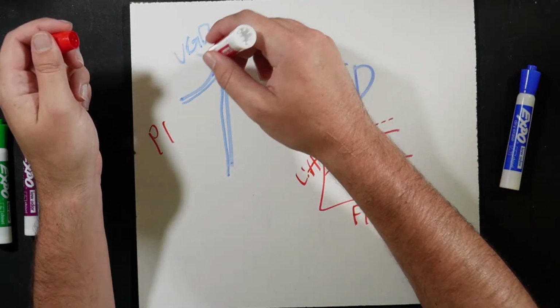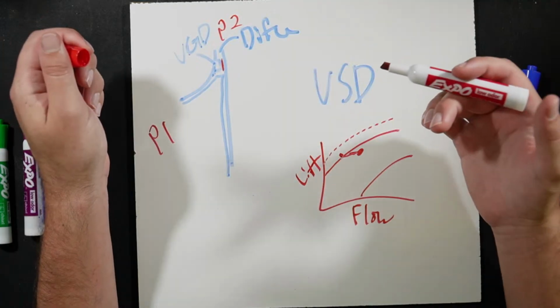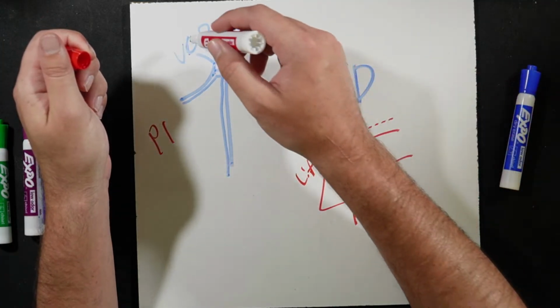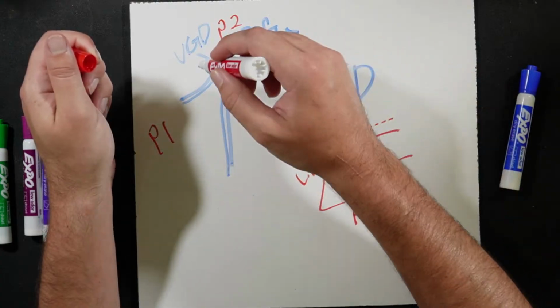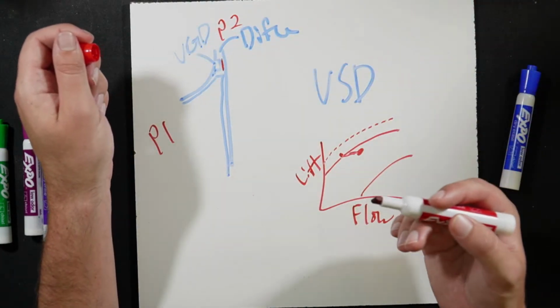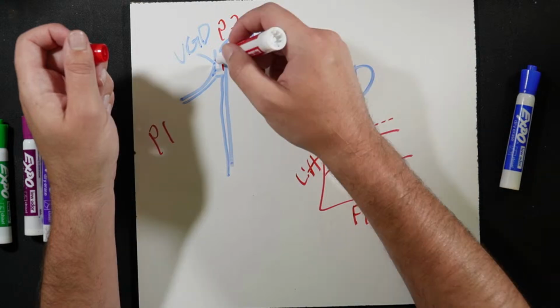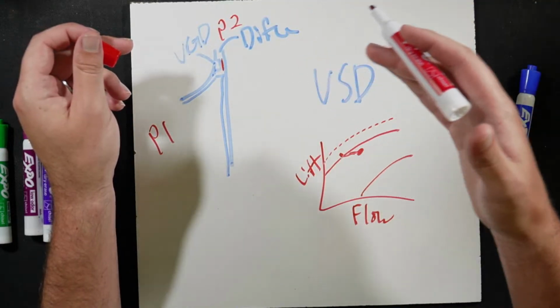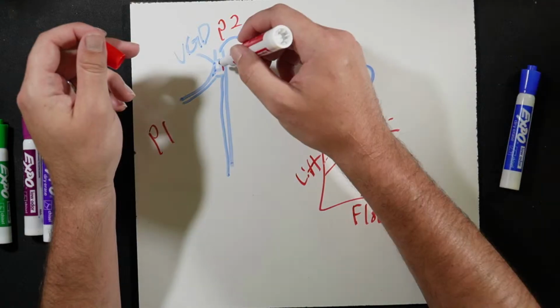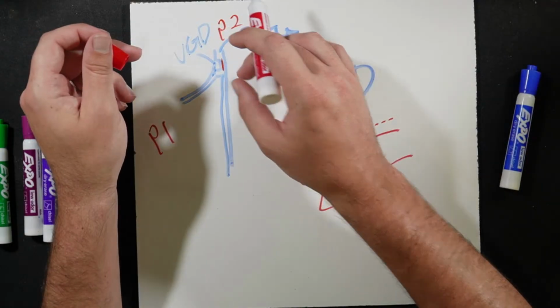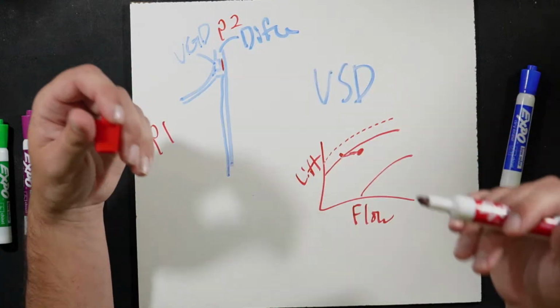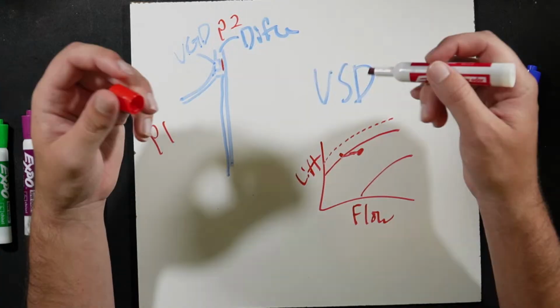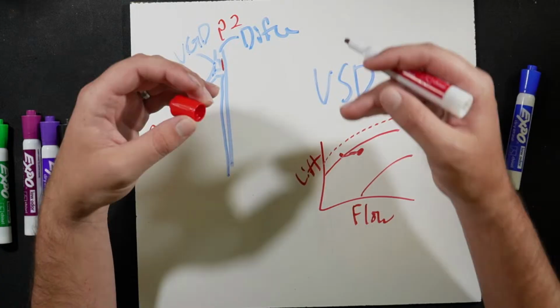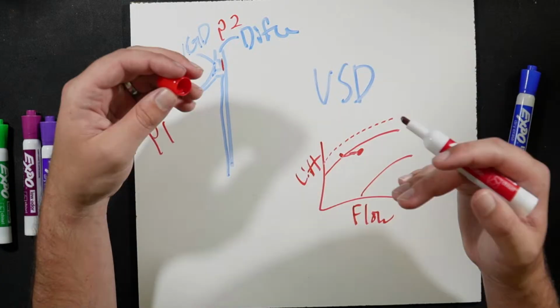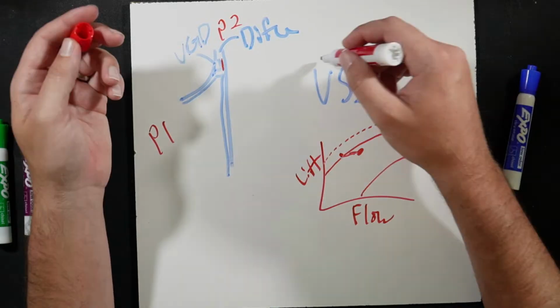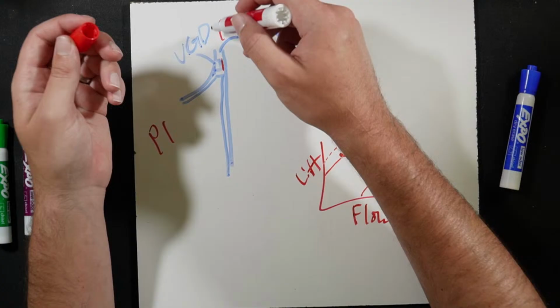And that is why some of these chillers do not have an inlet guide vane, an IGV. They only have a VGD with a drive. And part of that VGD's process is, as that chiller is unloading, we push the VGD to a closed position, which narrows our diffuser gap, reducing how much flow goes through there.